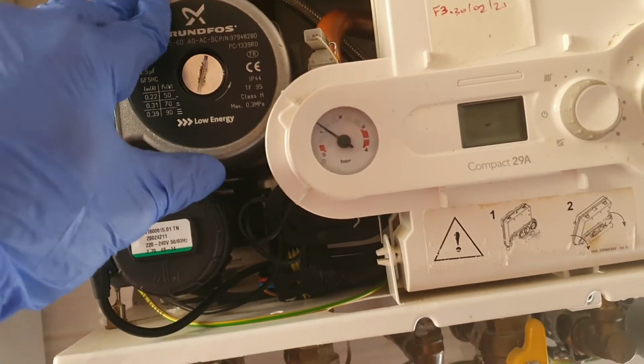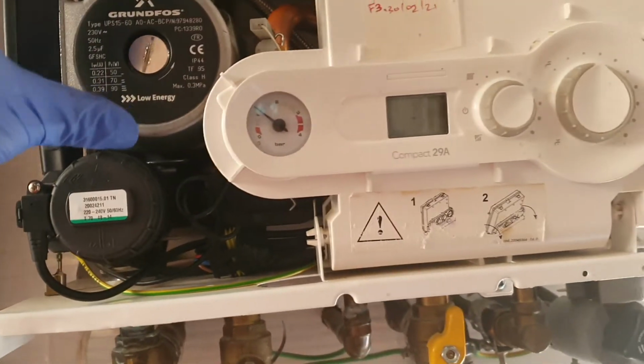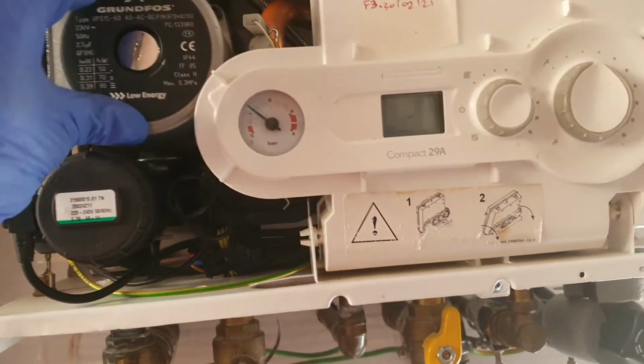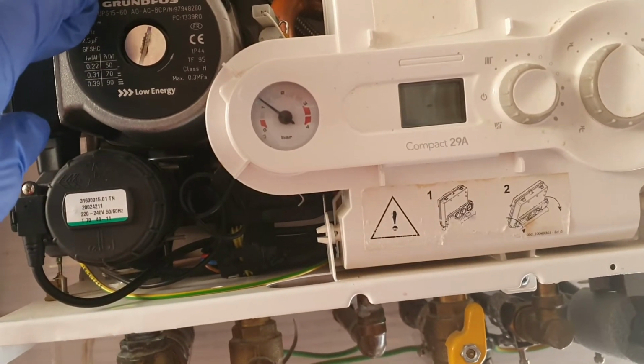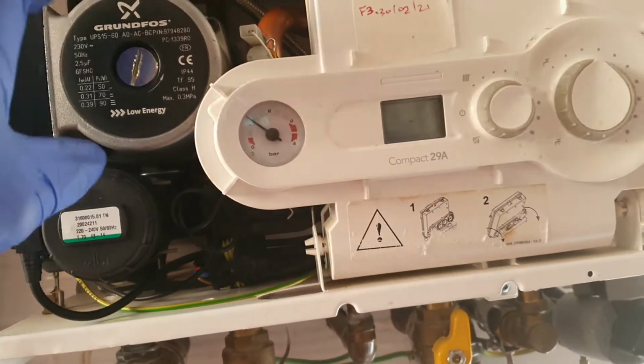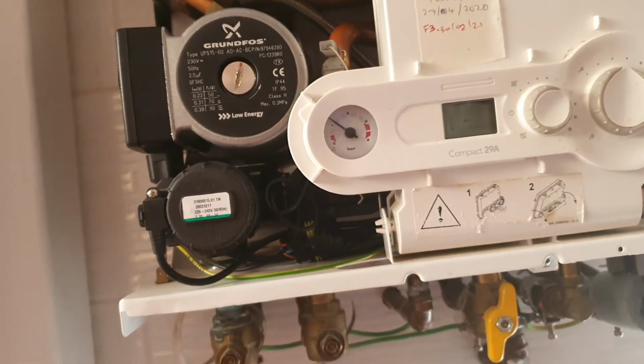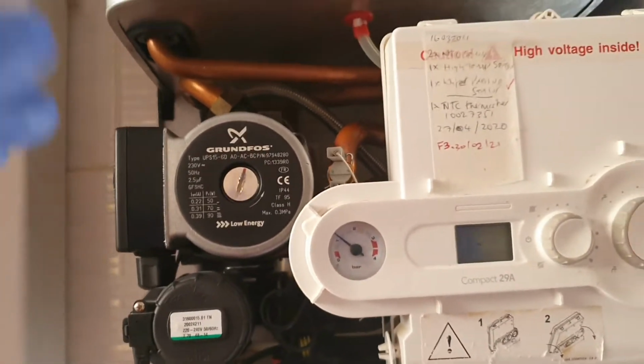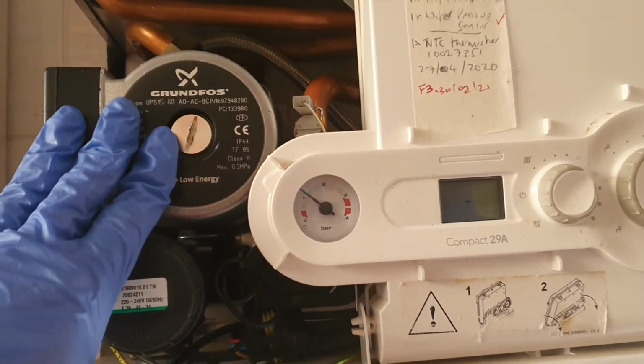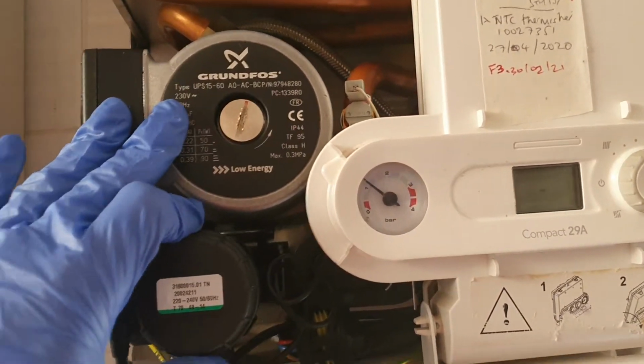So that's that, and as I said, this needs replacing. 10 years it's had its life, constantly being used. So I've got a brand new unit. The reason why I'm replacing this is it's causing a lot of humming noise, travelling through the copper pipe towards the front of the property, upstairs bedroom, and you can hear it humming away like an absolute monster truck basically.